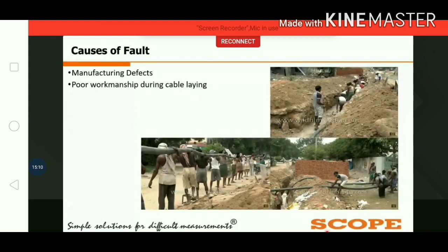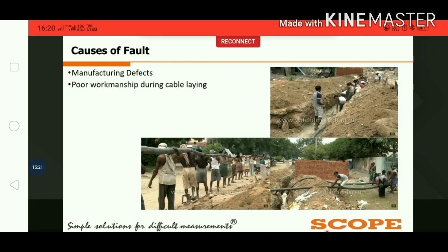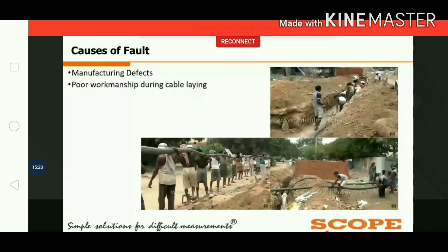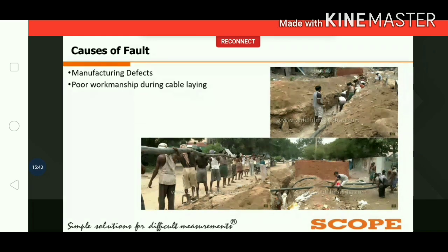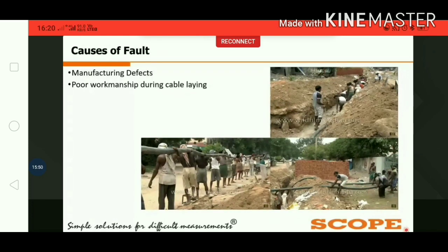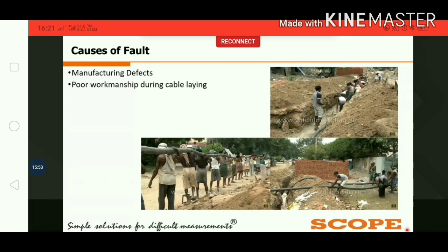Another cause of cable damage is poor workmanship during cable laying. In India, manual cable laying is widely used. As seen in the picture, proper care of the bending radius is not always taken during installation. If proper care is not taken, the armor of the cable gets damaged or cracked at the bending point, leading to further damage of the cable.